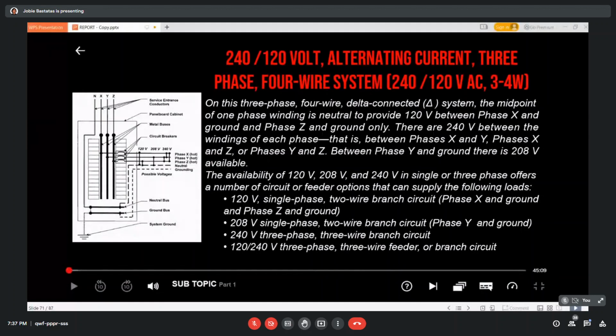So last is the 240/120 volts alternating current three-phase four-wire system. This is another fairly common electrical service found in commercial and industrial buildings where three-phase motors above 1 to 2 horsepower and equipment such as large air conditioners are used.